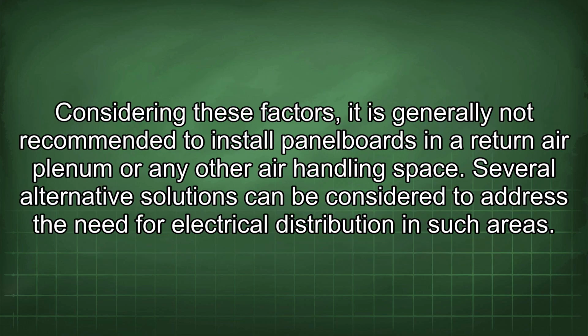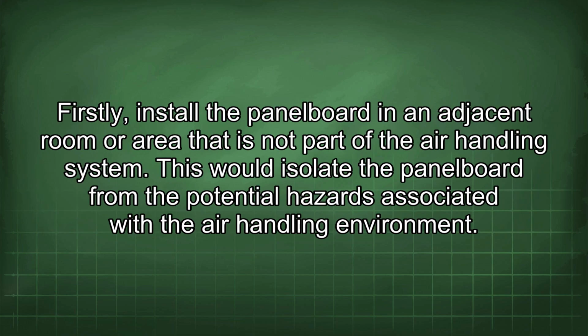Considering these factors, it is generally not recommended to install panelboards in a return air plenum or any other air handling space. Several alternative solutions can be considered to address the need for electrical distribution in such areas. Firstly, install the panelboard in an adjacent room or area that is not part of the air handling system. This would isolate the panelboard from the potential hazards associated with the air handling environment.